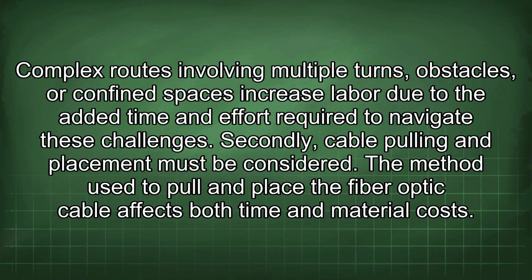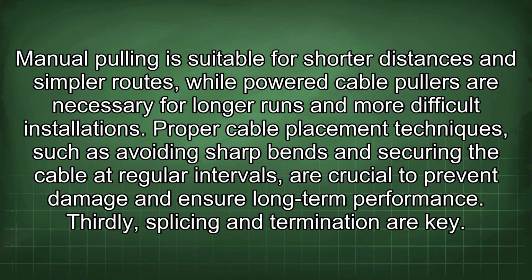Secondly, cable pulling and placement must be considered. The method used to pull and place the fiber optic cable affects both time and material costs. Manual pulling is suitable for shorter distances and simpler routes, while powered cable pullers are necessary for longer runs and more difficult installations. Proper cable placement techniques, such as avoiding sharp bends and securing the cable at regular intervals, are crucial to prevent damage and ensure long-term performance.